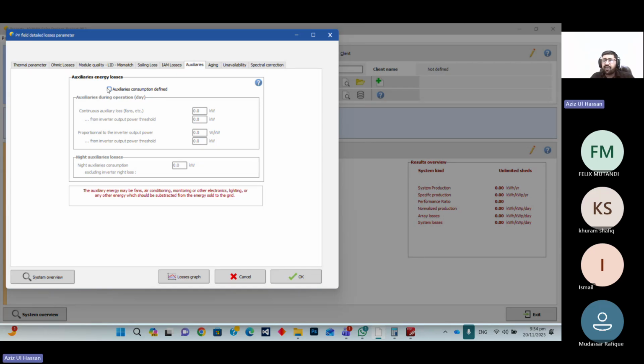Like the MV station, they have UPS systems available for their SCADA options and other things. They will take power from the auxiliary transformer available inside the MV skid, and they will charge through those 400 volt transformers. So that is why we have to put some value for the auxiliary fans, like output power, and some night auxiliary losses through the UPS. So we just put 10 kilowatt as the value.